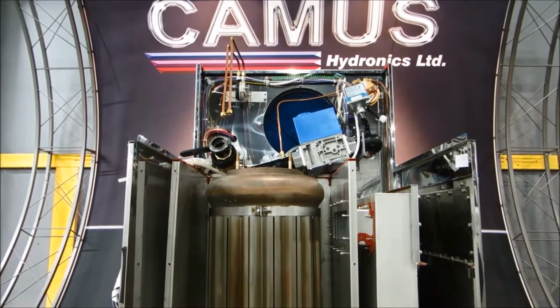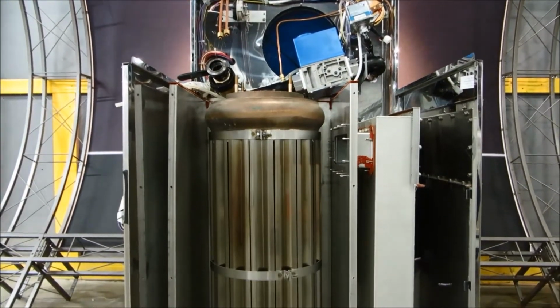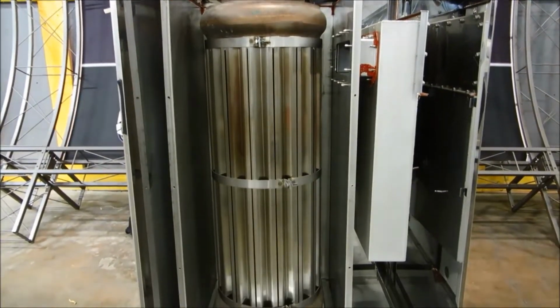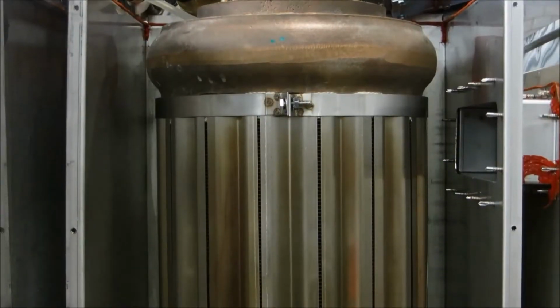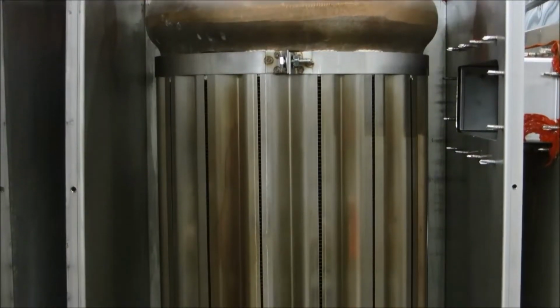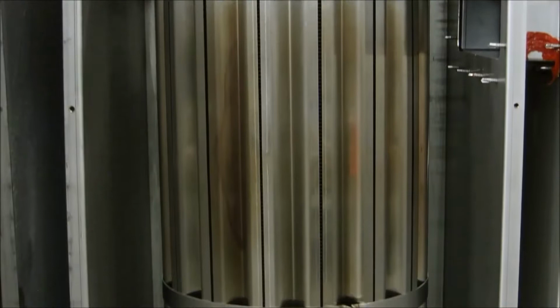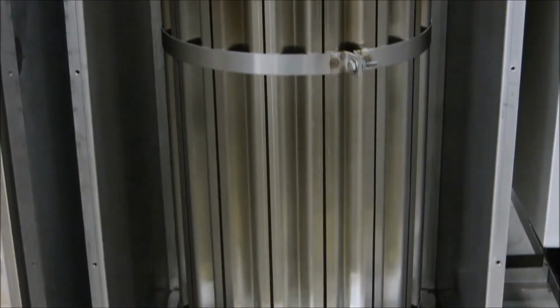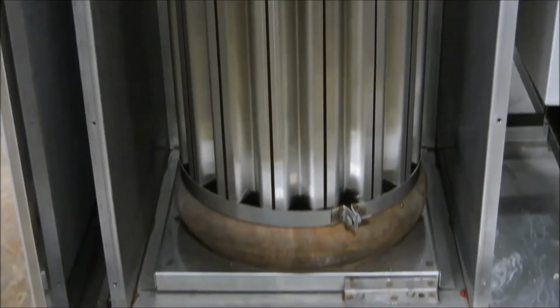When cleaning the Dynaflame copper heat exchanger is required, leave all V-baffles in place and using the wand from a pressure washer clean the heat exchanger from inside out and from top to bottom. In the case of a Dynaflame stainless steel heat exchanger, remove all V-baffles and use the same method as described before. Disconnect the condensate neutralizer box if equipped before cleaning.